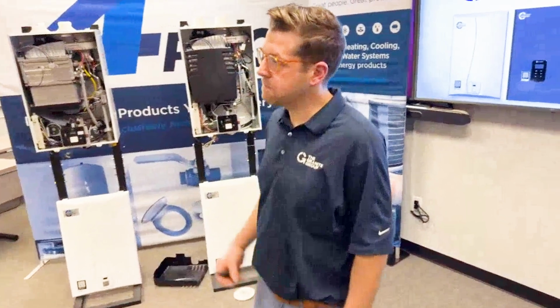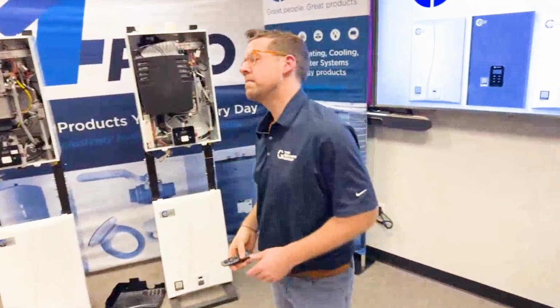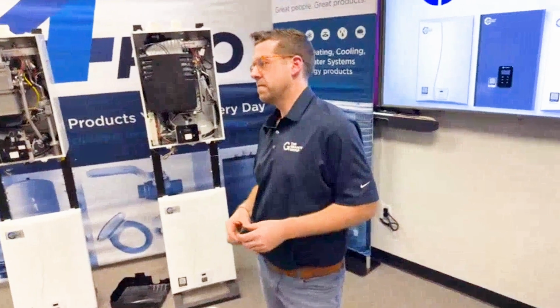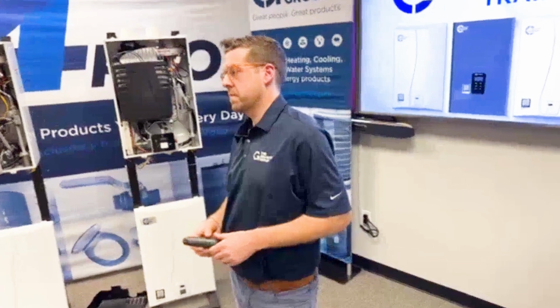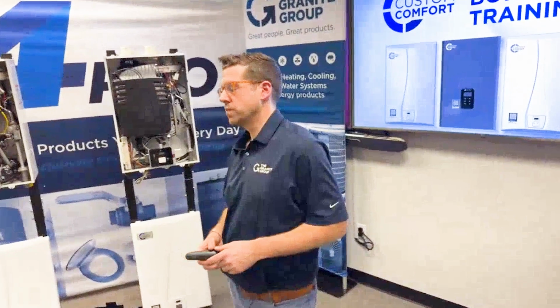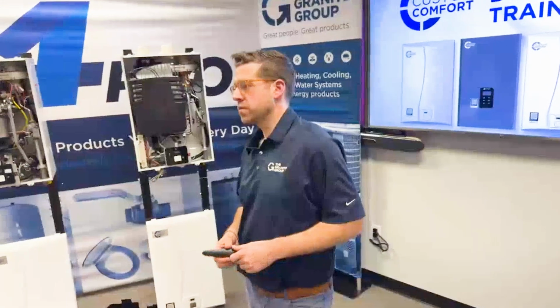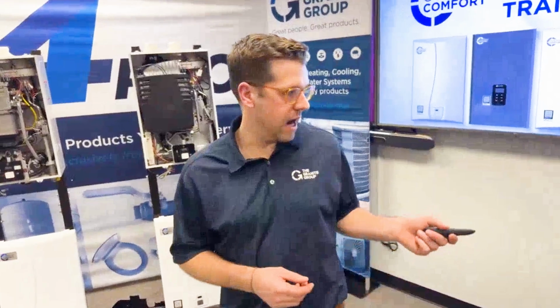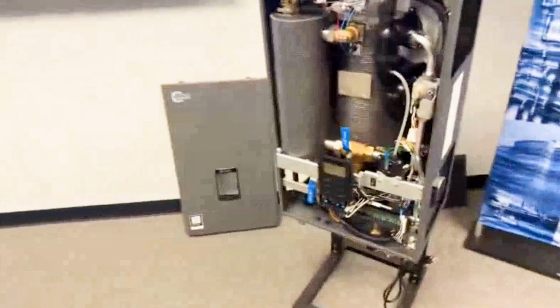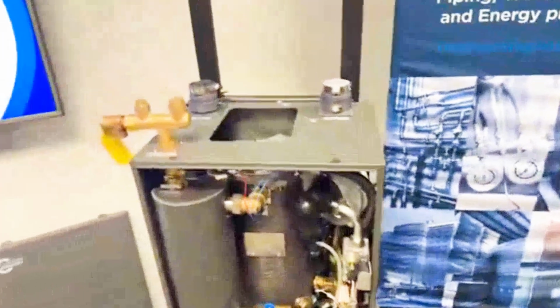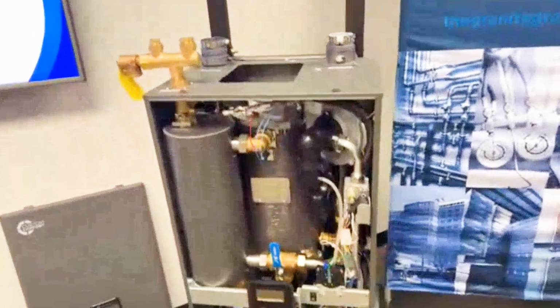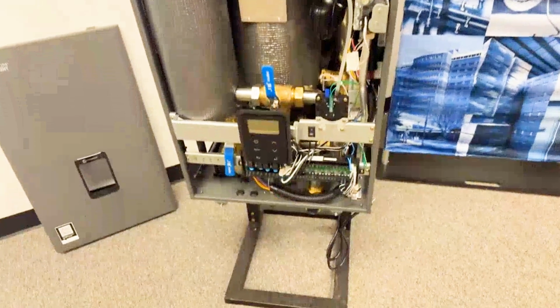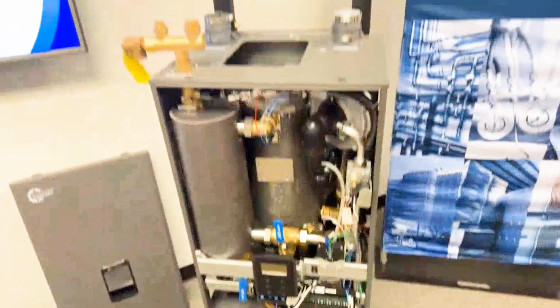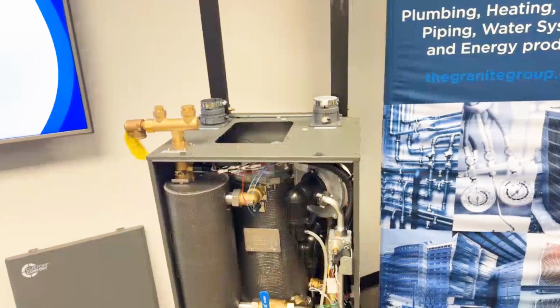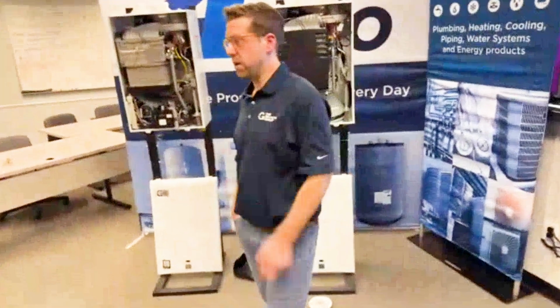Excellent. And then we're back to venting. Does this need 2 feet of straight? In two situations, do you need 2 feet straight before any elbows? So venting on the fire tube, we would like to see 12 inches of 2-inch off the top of the fire tube before making one of those transitions, whether it be to 3-inch or a 90 or 45. Similar to the first series boiler, we would prefer to see 12 inches of 2-inch venting off the top. Yep, 1 foot, not 2 foot.